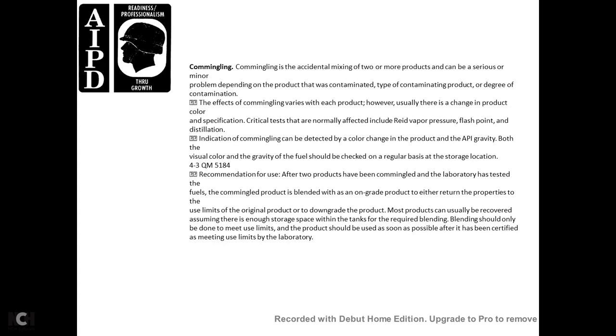Commingling is the accidental mixing of two or more products. Effects can be serious or minor depending on the product contaminated, the type of contaminating product, and the degree of contamination. Usually there is a change in product color and specification critical test results. Tests normally affected include the Reid vapor pressure, flash point, and distillation. Commingling can be detected by changes in product color and API gravity. Recommendation: after commingling, test the blended product; if it meets the use limits of the original product grade, it may be downgraded. Most products can be recovered assuming enough storage space is available for blending.